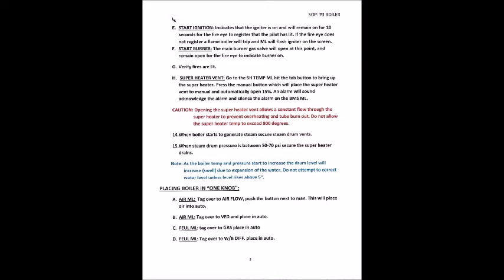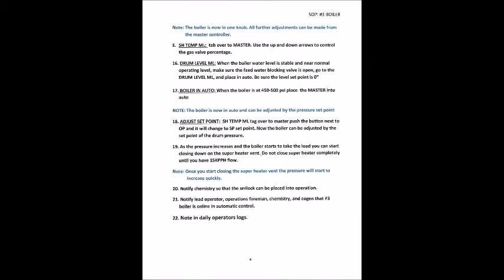Placing boiler in one knob. A. Air ML. Tab over to the airflow, push the button next to man. This will place air into auto. B. Air ML. Tab over to VFD and place in auto. C. Fuel ML. Tab over to gas, place in auto. D. Fuel ML. Tab over to WB diff, place into auto. Note, the boiler now is in one knob. All further adjustments can be made from the master controller. E. SH temp ML. Tab over to master, use the up and down arrows to control the gas valve %.